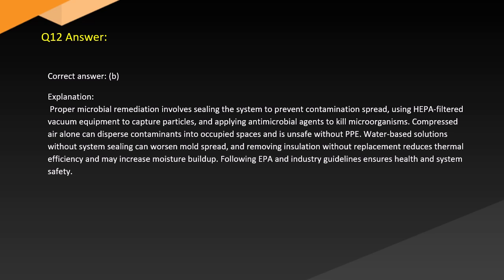Answer. Correct answer: B. Explanation. Proper microbial remediation involves sealing the system to prevent contamination spread, using HEPA filter vacuum equipment to capture particles, and applying antimicrobial agents to kill microorganisms. Compressed air alone can disperse contaminants into occupied spaces and is unsafe without PPE. Water-based solutions without system sealing can worsen mold spread, and removing insulation without replacement reduces thermal efficiency and may increase moisture buildup. Following EPA and industry guidelines ensures health and system safety.